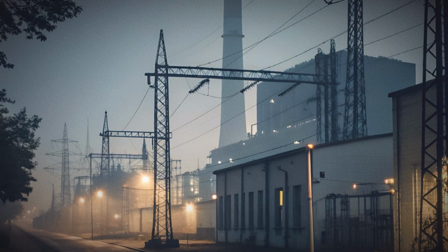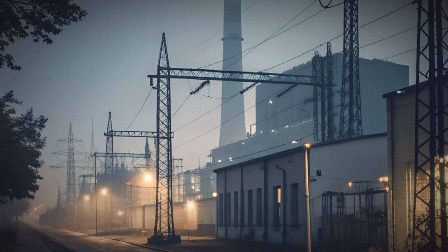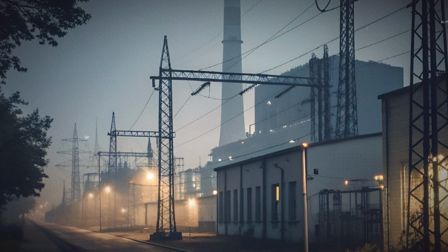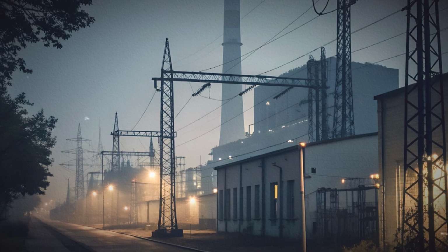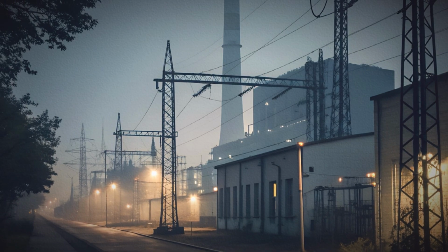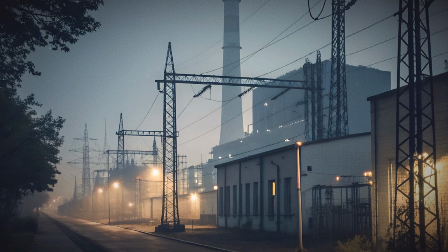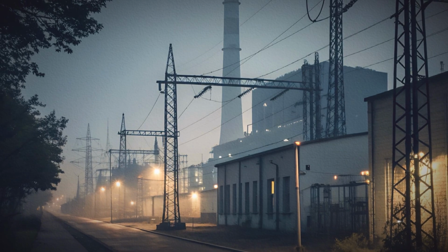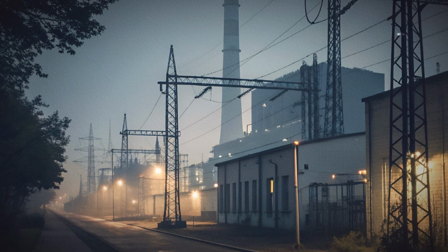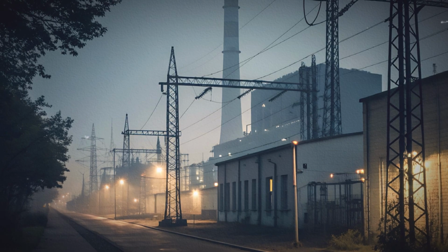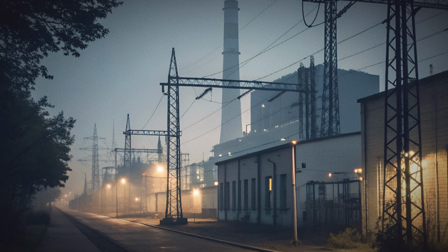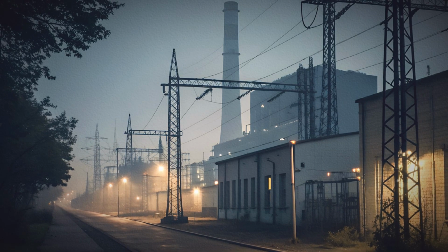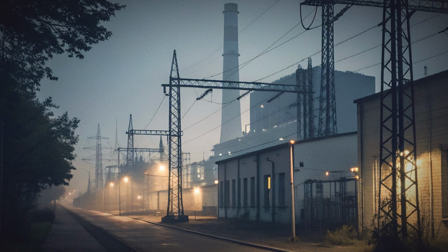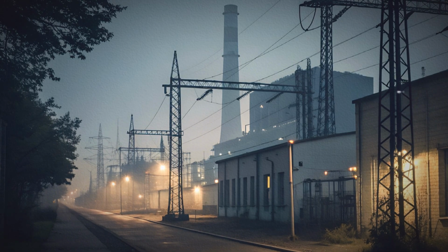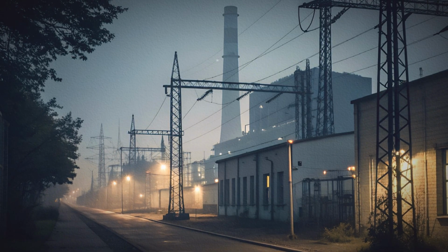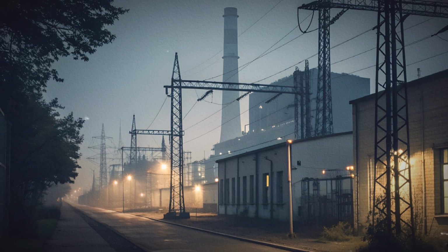Hydroelectric plants use flowing water to turn turbines directly. Wind plants use wind-driven blades to turn generators. Solar plants produce direct current, which is converted to alternating current by inverters. Each generator or inverter is connected to the grid through transformer equipment. Transformers step electrical voltage up for efficient transmission and down for local distribution.